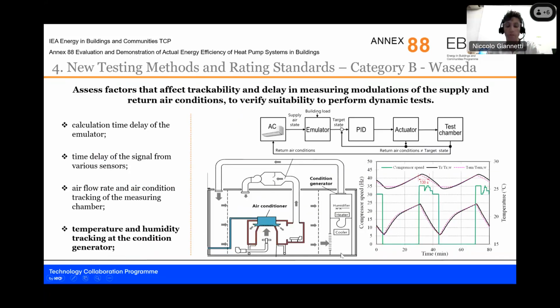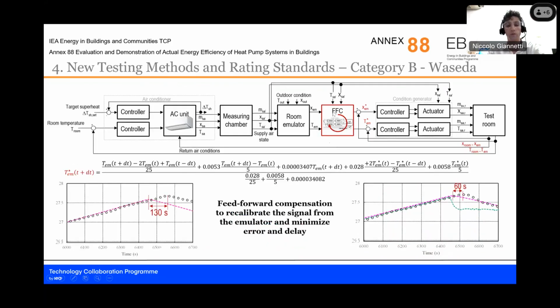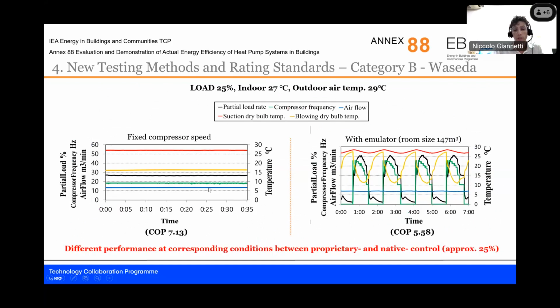Okay, other delay could come from the condition generator itself, and we developed a feed-forward compensation method that models the delay and, with a simple linear model, reverses the calculation to minimize this delay and offsets during dynamic operation. This is not necessary to be used, it is only required whenever the reconditioning unit has substantial delay. This is an example of the result that we can obtain in corresponding conditions. So fixed compressor speed results and emulator type load-based test results. The COP is substantially different, over 25% difference in low load conditions, such as this one, so 25% load.